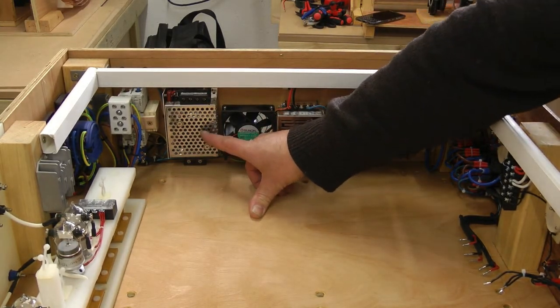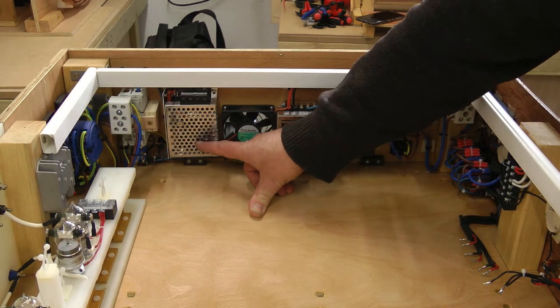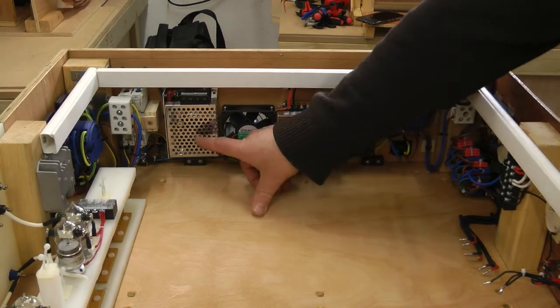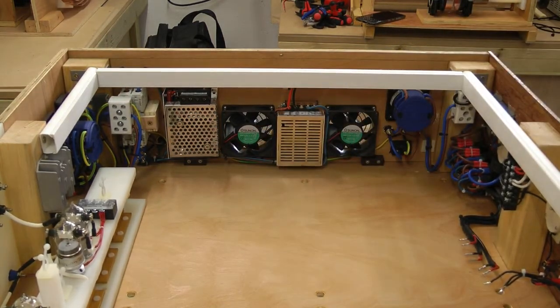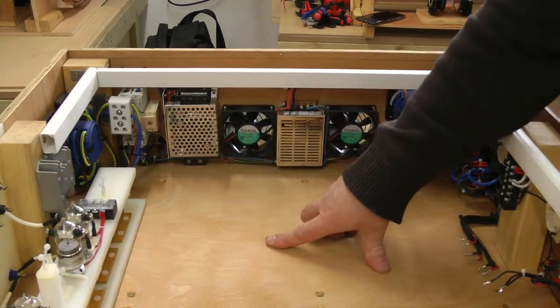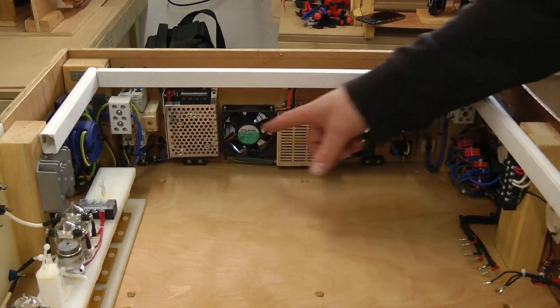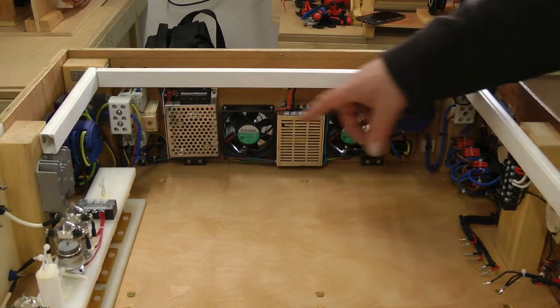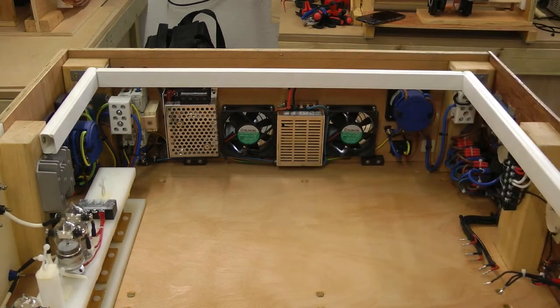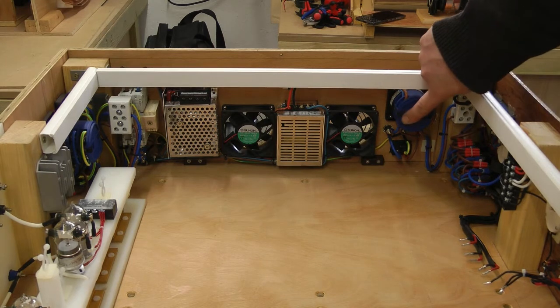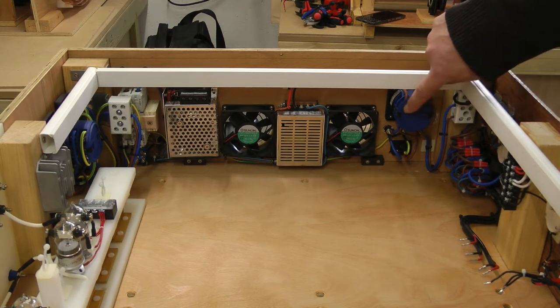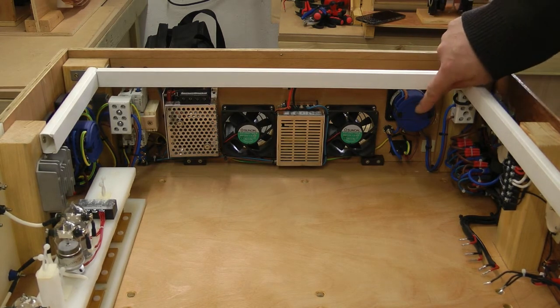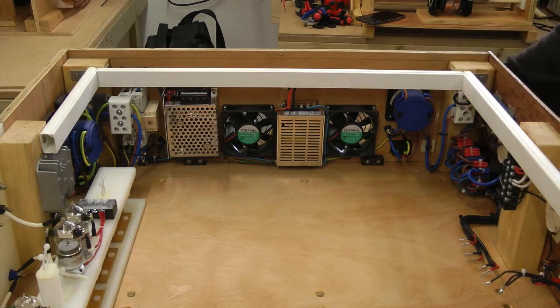The internal SCR, this is nominally, well, it's called a 10 kilowatt SCR. I think it's really good for about 4 to 5 kilowatts continuous. That's got its own fan inside. There is the dual cooling fans, which line up in between the transformers, so they pass air across the transformers and across all the other components and vent on the left hand side. Then there's the line source select double pole switch, which either switches on the panel to SCR or to an external line supply source, which might be, for example, a variac or some other kind of power control.